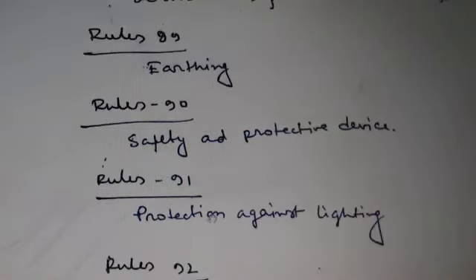Rule number 91 is related with the protection against lightning. Under this rule, the following points are: the owner of every overhead line which is so exposed as to be the cause of injury from lightning shall adopt an efficient manner for discharging to earth any electrical surge due to the lightning. Next point, the earthing lead for any lightning arrester shall not be passed through any iron or steel pipe, but shall be taken as directly as possible from the lightning arrester to a separate earth electrode, subject to the avoiding of any accident.